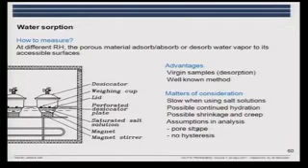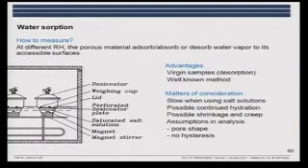And then there are some assumptions in connection with the analysis, that's the pore shape. That's the same for the other methods also, that you make assumptions on the shape of the pores to do the calculation. Pressure to pore size, or freezing temperature to pore size, and here vapor pressure to pore size. And then you also have to make some assumptions of the hysteresis, or no hysteresis.